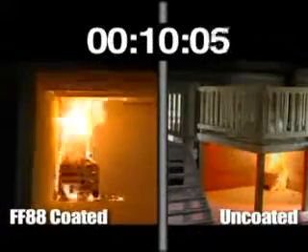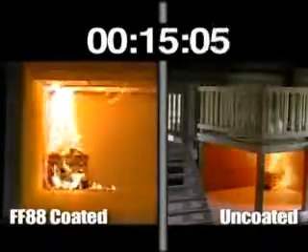The test is a comparison of two simulated school lofts, six foot square with a subfloor four foot above the floor. The fuel and ignition source is a 20 pound wood crib set in one corner of the room. The methodology used is similar to the room corner test for UL 1715 and Factory Mutual 4880, except that the fuel load was more severe than in an actual room corner test.